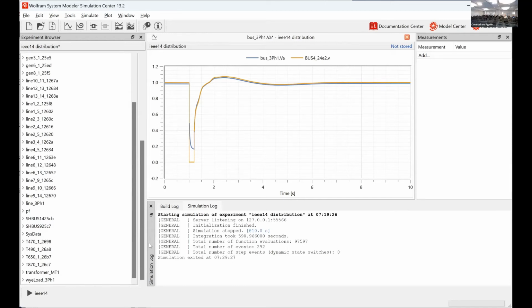In this case, we put a fault on the line, which is kind of like if you're in an electric power system and somebody were to take a chain and throw it over the top of all 3 phases, landing on all of them at the same time. That would be a fault. The system is protected for that, but it would short the current to ground. This shorts the voltage to ground, and you see a dip in the voltage before it goes back up. What you'd see in terms of lights is your lights would dim or go off.